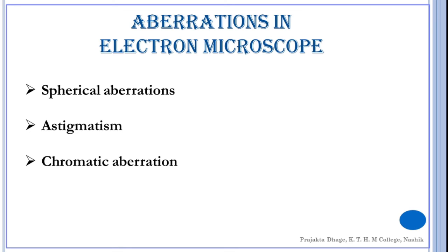An image having astigmatic aberration shows two sharp images diametrically at right angles to each other at two different focusing levels. It is all the more obvious at high magnification, when small defects in the optical system become more obvious. Astigmatism can be corrected by introducing radial iron screws which correct the inner diameter of the bore on the magnetic coil. This defect is taken care of and is not observed in modern microscopes.